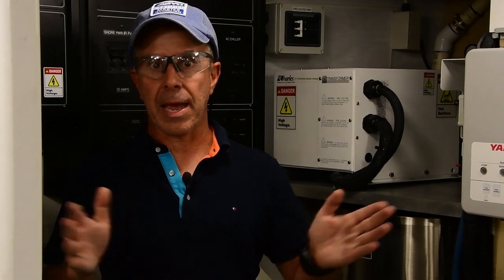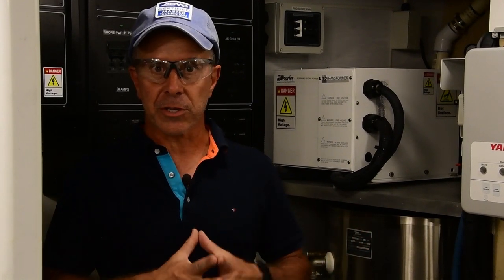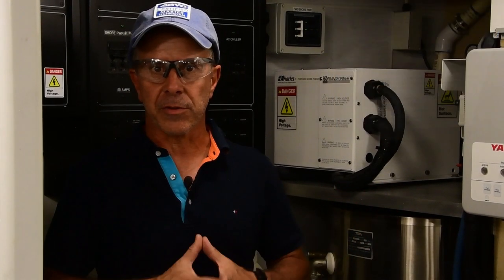You'd get to plug into that 120 volt shore power dock pedestal, and again, it would energize all of the circuits on the boat, not simultaneously, because you'd need to load manage, because you'd have the same wattage as if you were plugging into a conventional 120 volt 30 amp dock outlet, but you do get the benefit of at least choosing what you're going to run on the boat, whether it's 120 or 240. So I recommend, if you're considering a transformer installation, that you select that option of 120 volt or 240 volt primary. Switchgear has to be installed to determine which one you're plugging into, of course, and you need a separate inlet for the 120, but that's a relatively small investment in the scheme of things, and the benefit is definitely worthwhile.